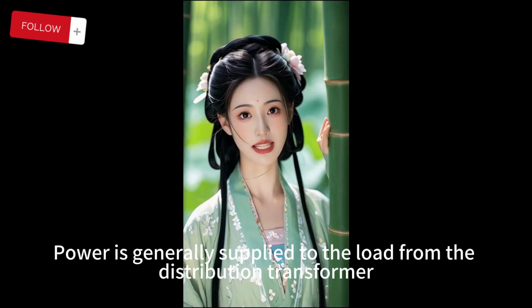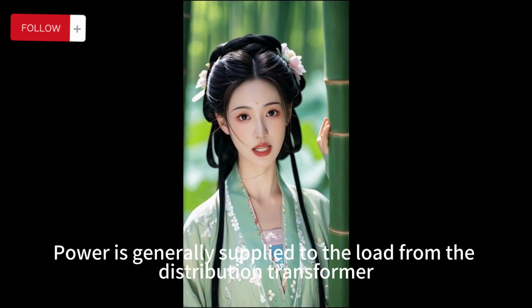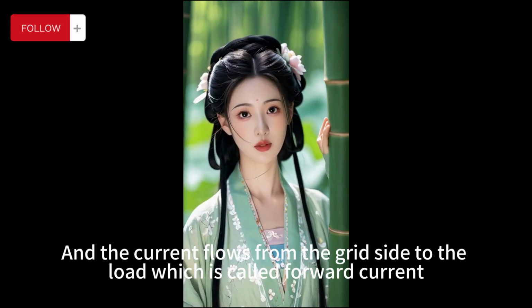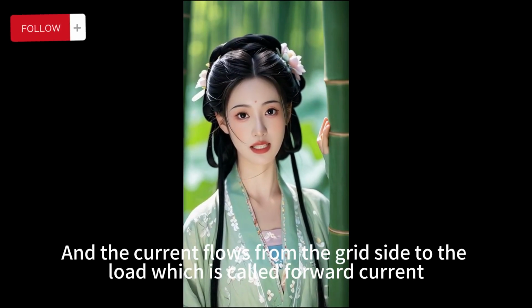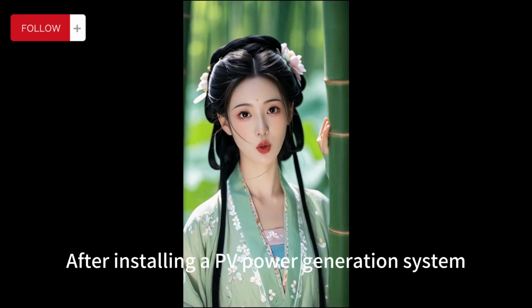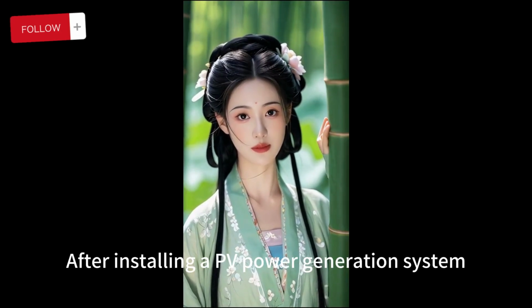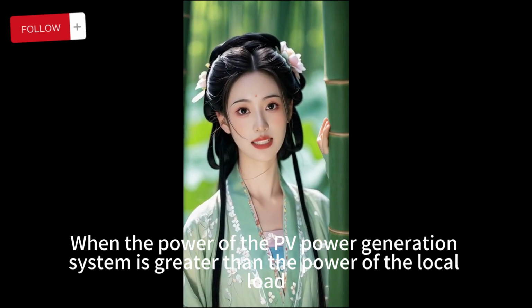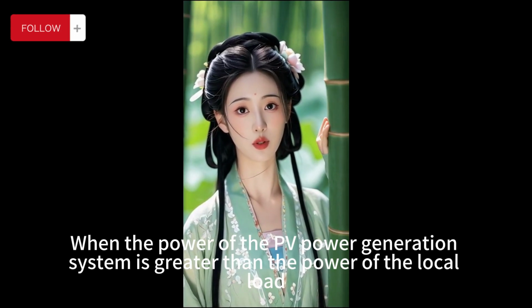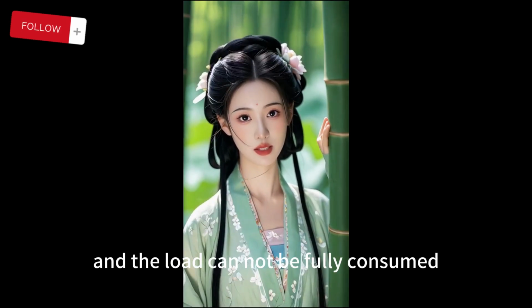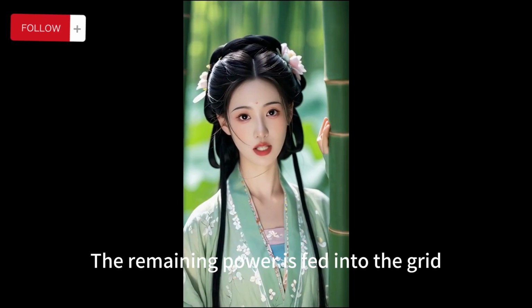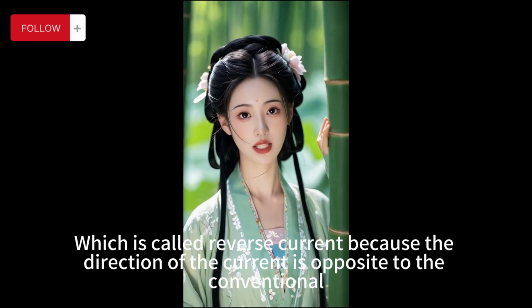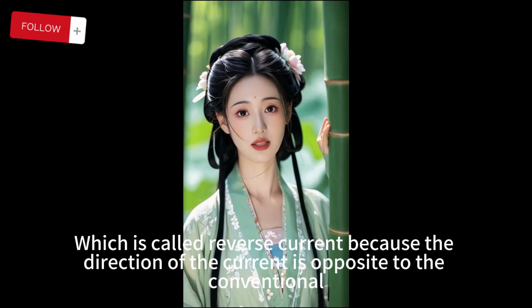In the traditional power supply and distribution system, power is generally supplied to the load from the distribution transformer, and the current flows from the grid side to the load, which is called forward current. After installing a PV power generation system, when the power of the PV system is greater than the power of the local load and the load cannot fully consume it, the remaining power is fed into the grid, which is called reverse current because the direction of the current is opposite to the conventional.